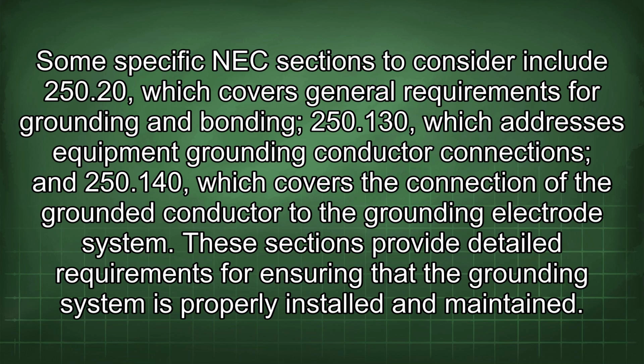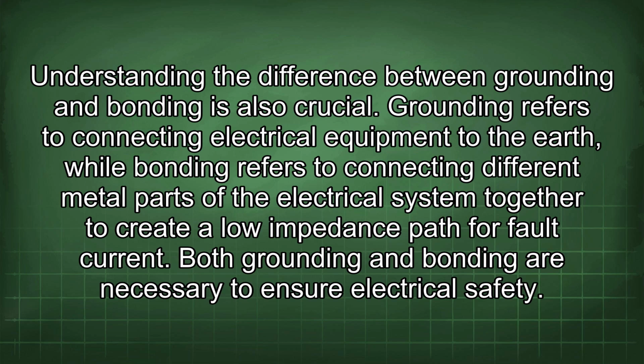Some specific NEC sections to consider include 250.20, which covers general requirements for grounding and bonding, 250.130, which addresses equipment grounding conductor connections, and 250.140, which covers the connection of the grounded conductor to the grounding electrode system. These sections provide detailed requirements for ensuring that the grounding system is properly installed and maintained. Understanding the difference between grounding and bonding is also crucial. Grounding refers to connecting electrical equipment to the earth, while bonding refers to connecting different metal parts of the electrical system together to create a low impedance path for fault current. Both grounding and bonding are necessary to ensure electrical safety.